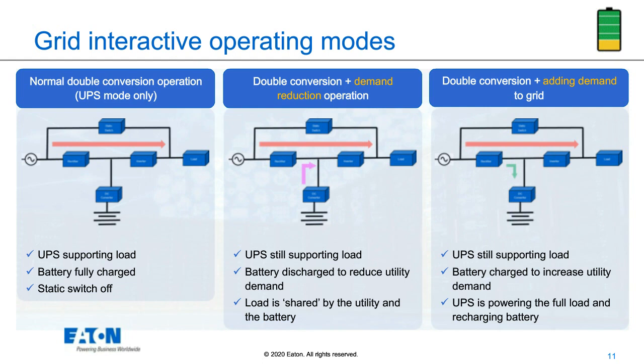In this operation, we do have the option with lithium batteries to maintain the battery system at about an 80% state of charge or less. That gives us some headroom to charge the batteries during times where we need to add demand to the grid. The first thing that comes to mind is that this battery and UPS's number one priority is to provide X number of minutes of backup time for my data center, and I don't want to be messing around with that.